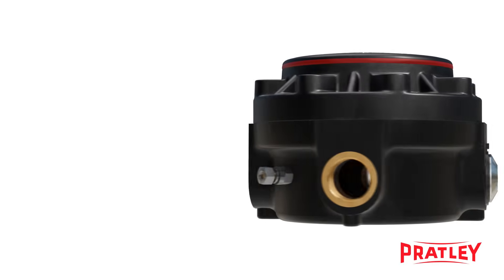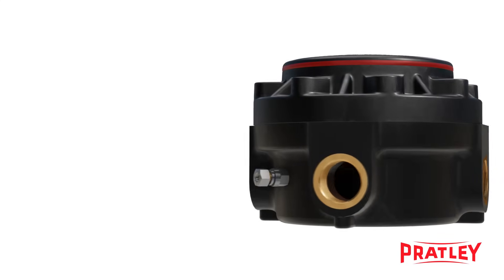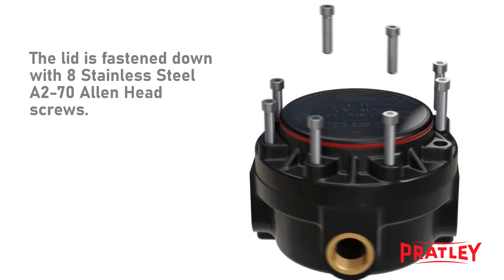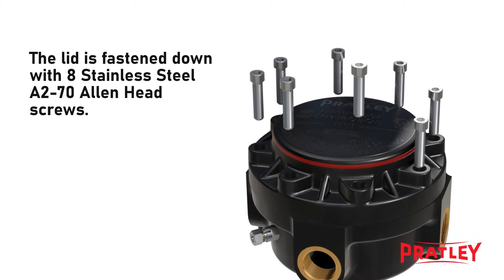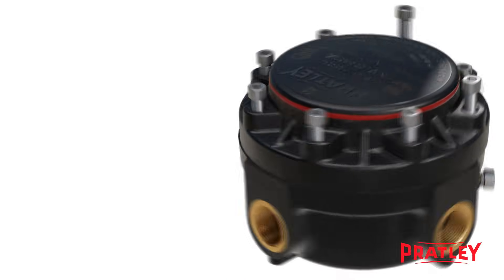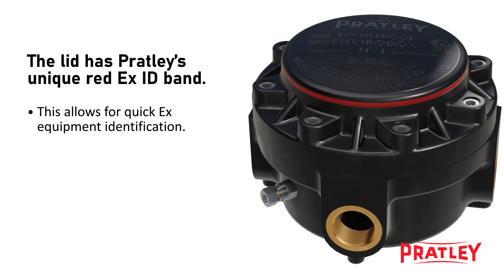Each box is supplied as a standard two-way box with two flameproof blanking plugs. The lid is fastened down with eight stainless steel A2-70 Allen head screws, contributing to the corrosion resistance of the junction box. The lid has Pratley's unique red EX identification band, allowing for quick EX equipment identification.